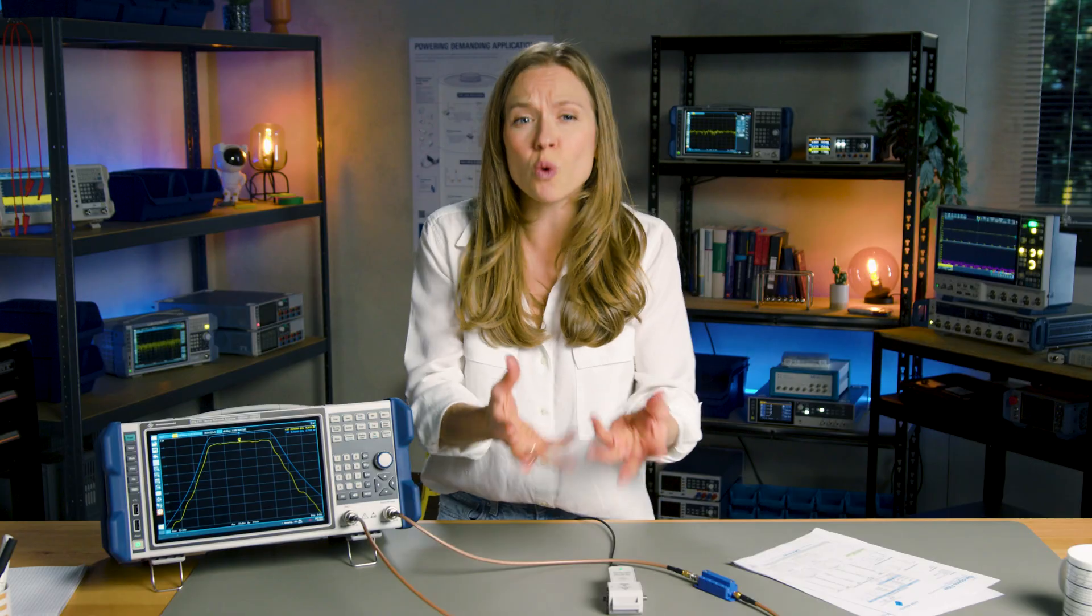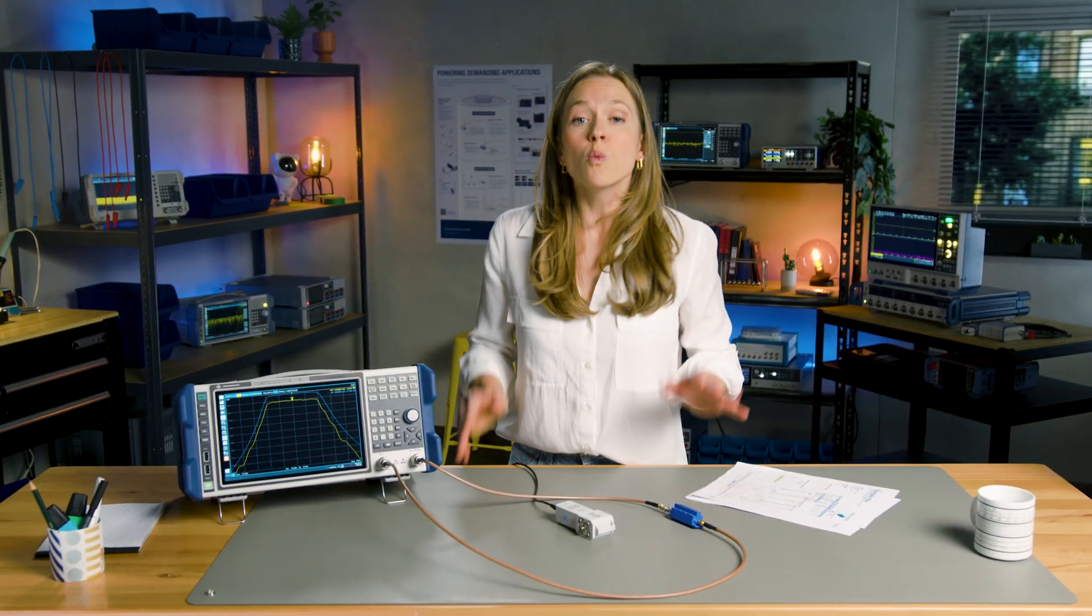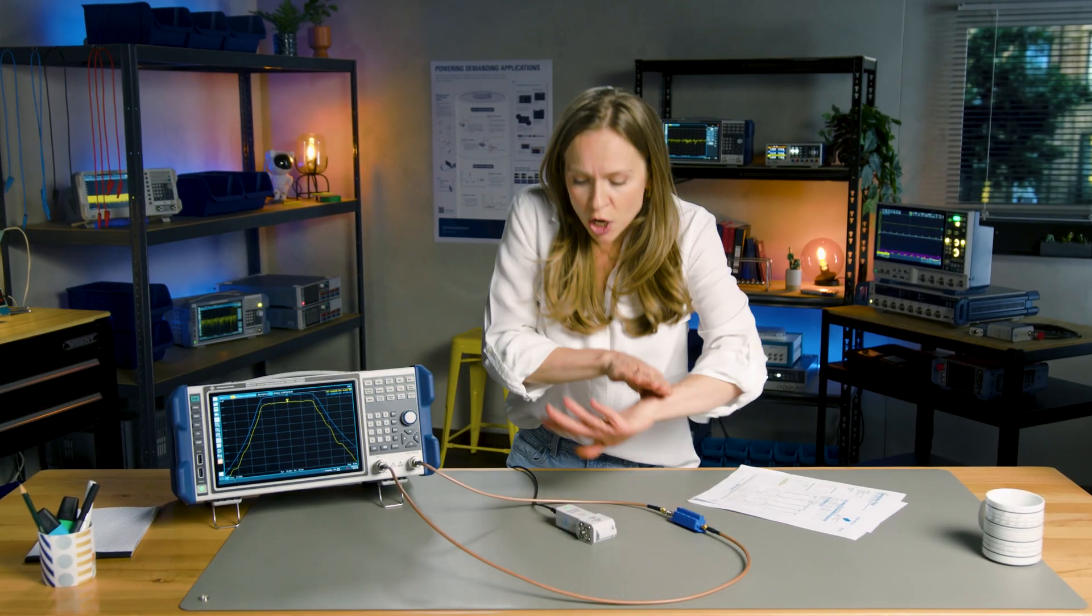A user calibration or system error correction is crucial to eliminate systematic errors within the measurement and remove unwanted effects of test cables and connectors to the DUT plane. Let's perform an automatic calibration.